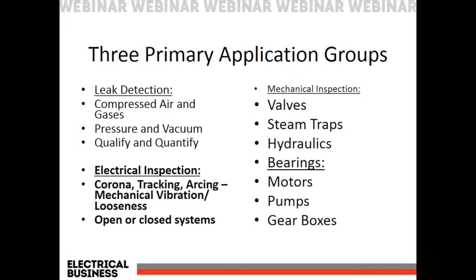I'll go to the side on the right where we're talking about mechanical stuff. On the mechanical side, we can also do valves, steam traps, and hydraulics. And with bearings, we can detect bearing defects and lubrication issues in motors, pumps, and gearboxes. So these are a lot of things that we can focus ultrasound on. But today, we're going to focus on the electrical inspection. Just to give a little segue, we're going to be looking at and being able to detect corona, tracking, and arcing, or even maybe a mechanical vibration or looseness in an electrical asset.